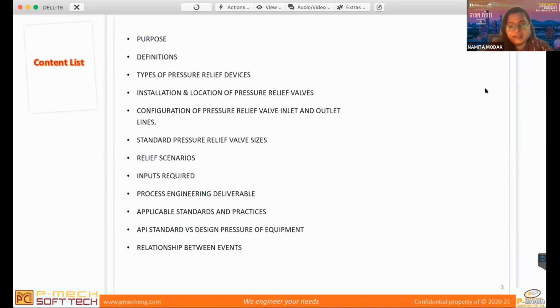So for the non-fire case, my overpressure will be 110% of your design pressure. 110% means it's 11 bar gauge. Okay. So that is the maximum pressure at which your PSV can relieve. It will start opening from 10 bar gauge, but full opening will be at 11 bar gauge. So that's the relieving pressure.